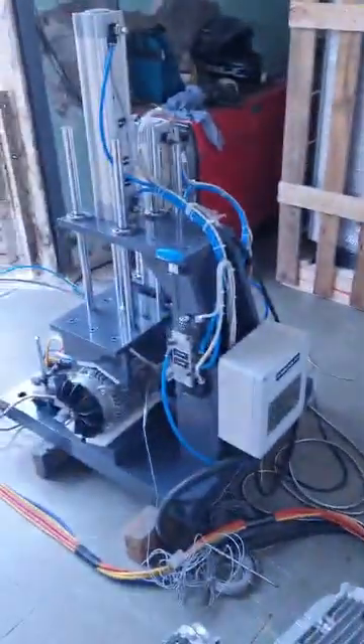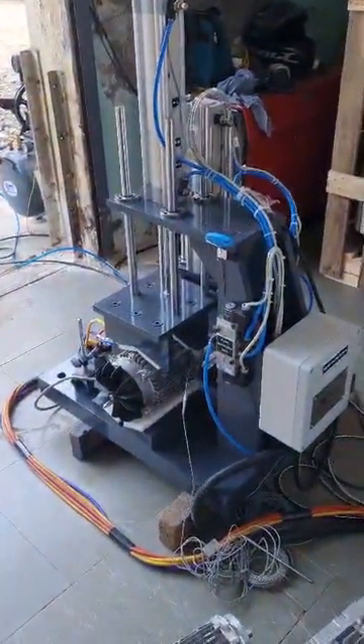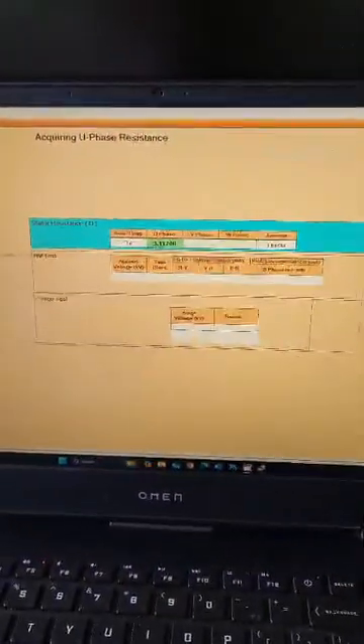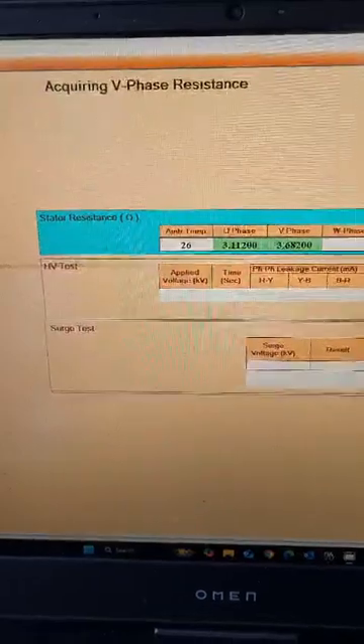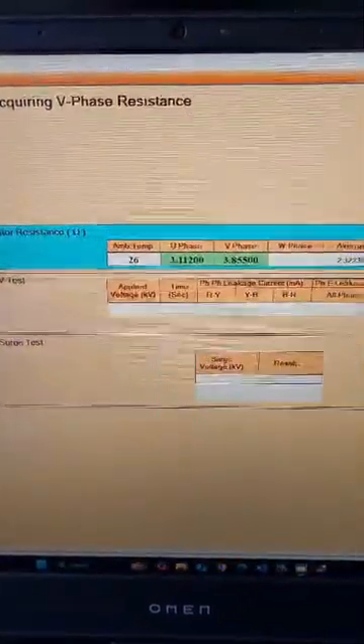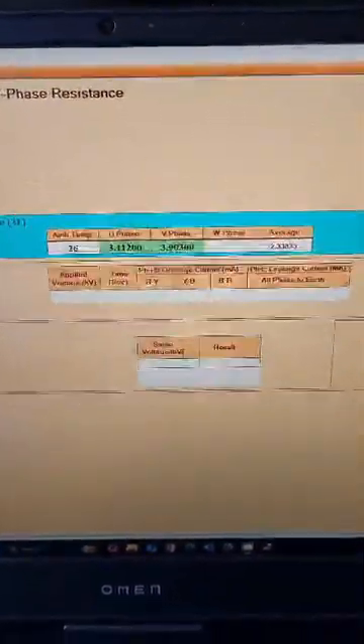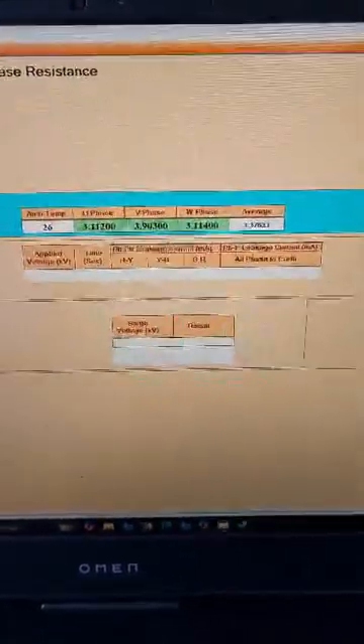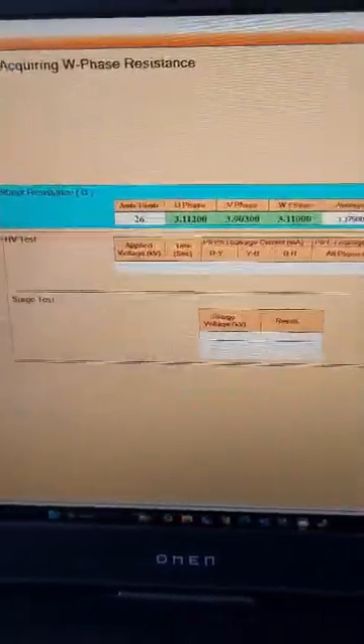Now let's click on the start test button on this particular screen, and the moment we do that, we'll be in a position to see the motor getting locked automatically there, and then you'll be in a position to see on the screen the stator resistance measurement happening, the ambient temperature coming automatically, the three phases, the winding resistance is measured and the average comes automatically.